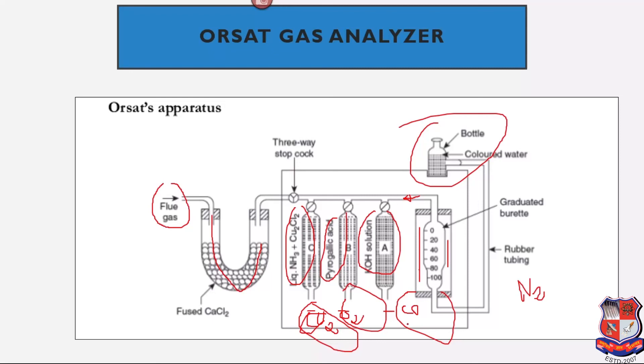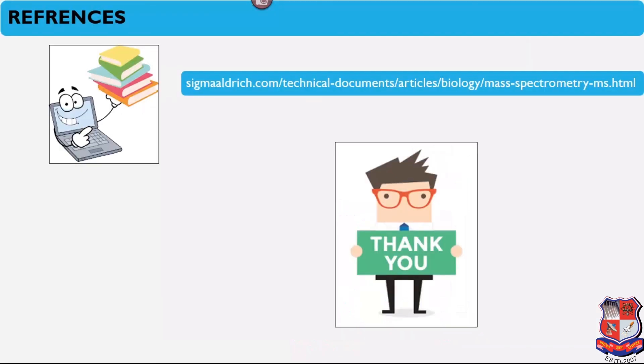From the results, we can determine combustion quality: if combustion is incomplete, the CO content will be high; if there is excess oxygen, the O2 value will be higher; and with complete combustion, the CO2 value will be higher. This is the Orsat gas analyzer, used to analyze the composition of flue gases — specifically CO, CO2, O2, and N2. Thank you for watching.